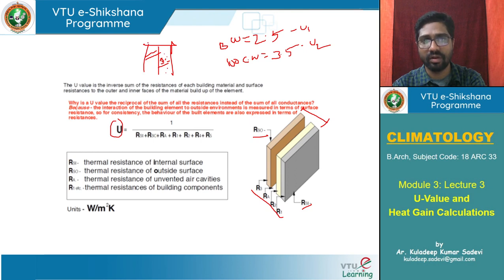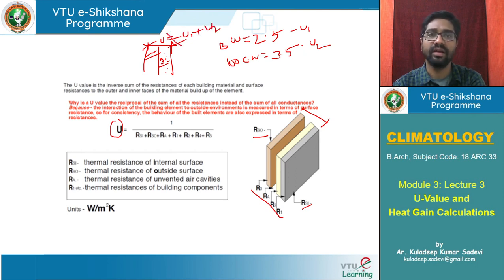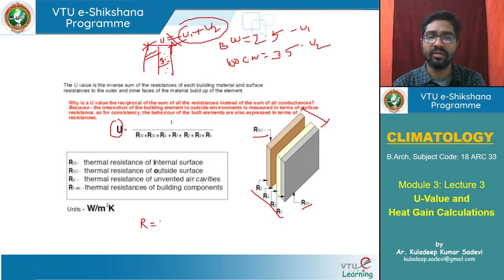The overall U-value of a combination of layers cannot be found by adding U1 plus U2 directly. We need to understand that conductance is not directly additive — only resistance is. So R_total = R1 + R2 + R3..., which also includes the outside surface resistance and the inner surface resistance. Once we know R, U = 1/R.